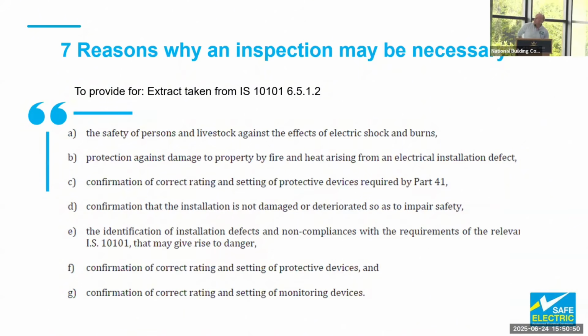So, reasons why an inspection may be necessary. Again, these are all extracted from the IS 10101 document. The safety of persons and livestock against the effects of electric shock and burns, protection against damage to property by fire and heat arising from electrical installation defects, confirmation of correct rating and setting of protective devices required by Part 4.1. So the protective device, in case you're wondering what we're referring to there, is your fuse or your MCB.